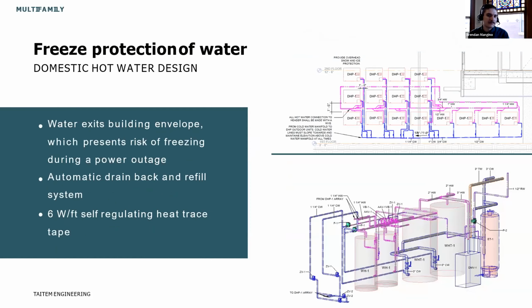So the first one, freeze protection. As I said, water exits the building envelope, and it presents a risk of freezing during really cold temperatures when the system's operable, but it presented a really large risk of freezing when the power went out, because you have this cold water sitting outside the envelope, just losing energy and getting close to freezing. To deal with the freezing risk during normal operation, we just added 2 inches of insulation and self-regulating heat trace tape. We have some data monitoring equipment on site over the course of the winter, and we saw that the heat trace tape only kicked on pretty rarely, only a couple minutes when it got really, really cold, below freezing. And it was only around 100 to 200 watts of power.